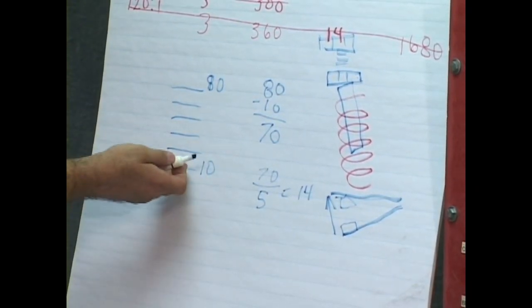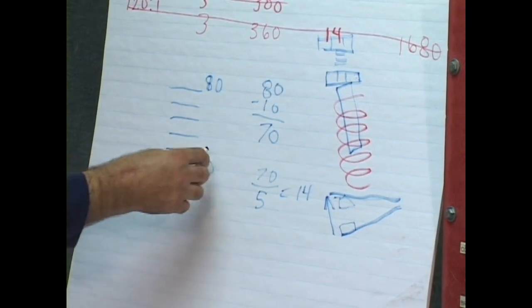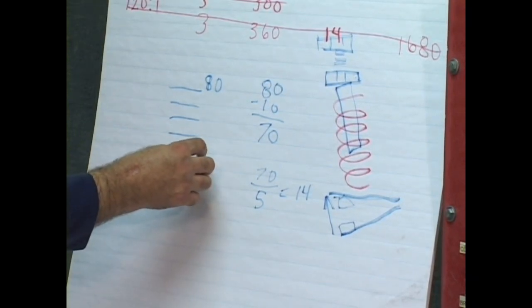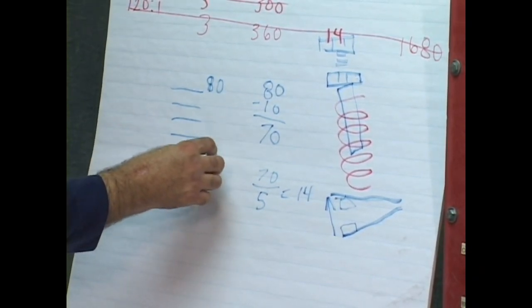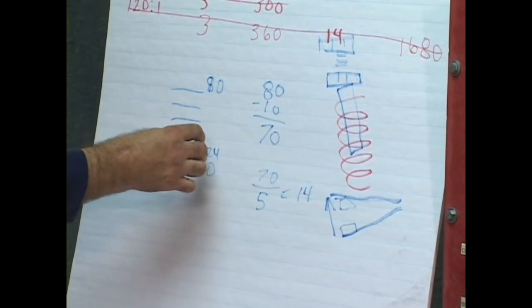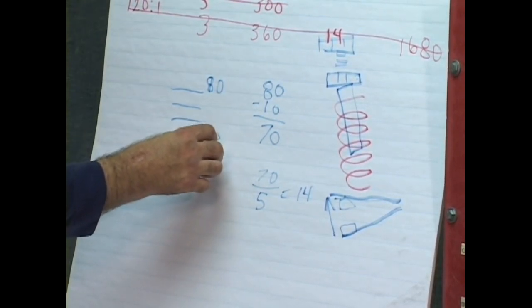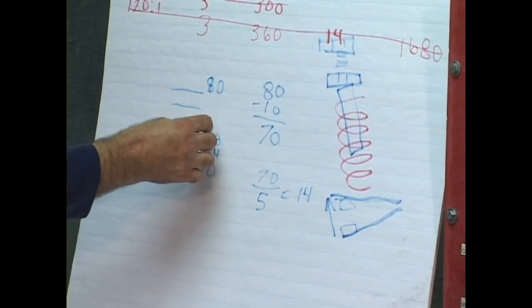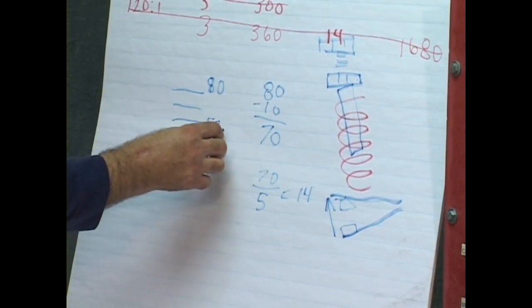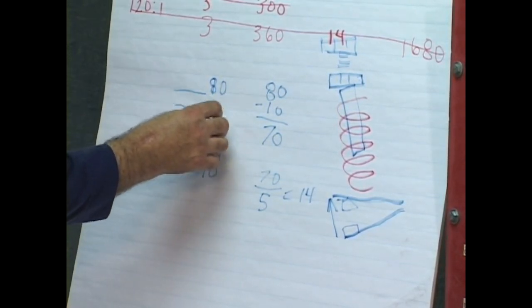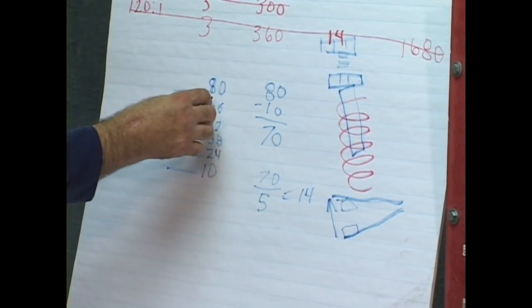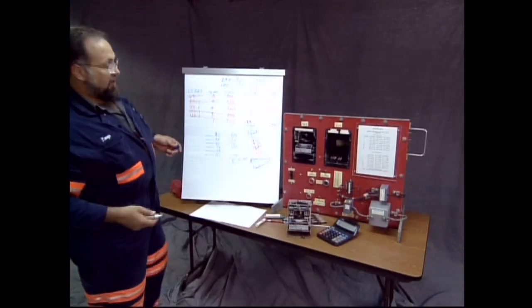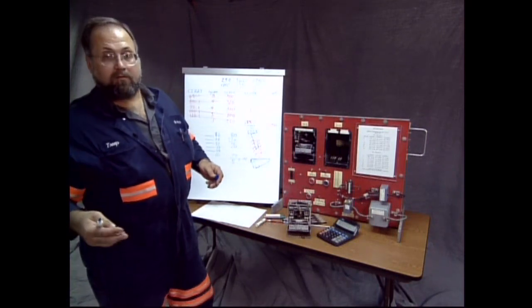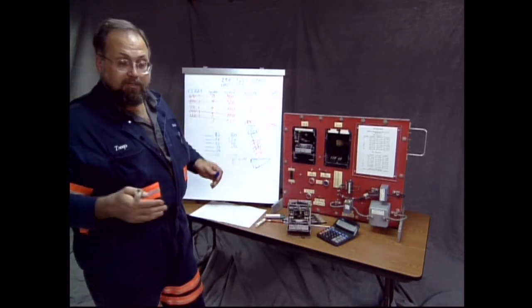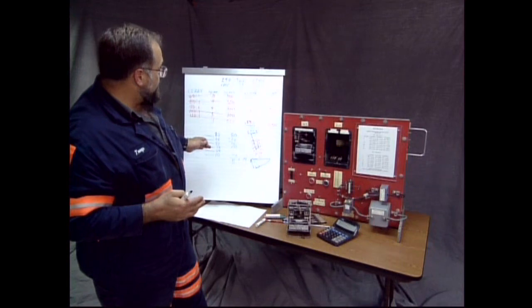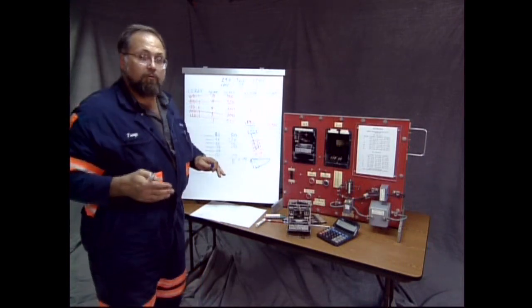So if I would adjust off the minimum one thickness of that bolt head right here, that would be add 14 to the minimum, 24. Another thickness, another 14, 38. Yet another one, 52. And the last one, 66. And then we would max out at 80 amps. Now again, this is not an exact science, doing this by field expedient adjustment. This will put you in the neighborhood.